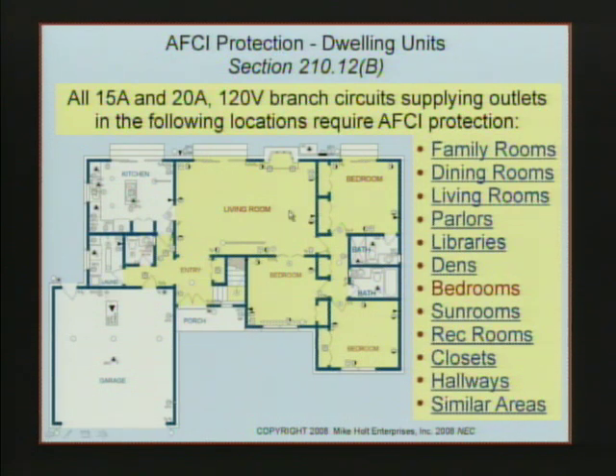Now, it doesn't apply to the kitchen. It doesn't apply to the bathrooms. It doesn't apply to the laundry room. It doesn't apply to garages. Now, the question comes up, okay, because kitchens have primarily what? GFCI protection on the countertop receptacles, right? And Steve, you taught us all that what? You have to have two small appliance circuits on those countertop circuits. The laundry receptacles do not have to have GFCI except those that are within 6 feet. Bathrooms do have to have GFCI. All the receptacles in the garage have to be GFCI protected, but the kitchen lights don't. So it's kind of crazy.